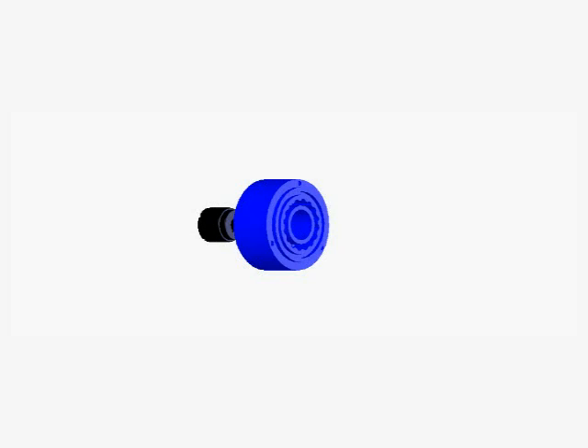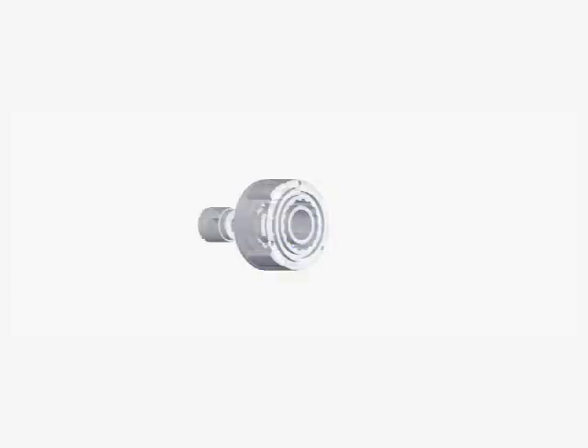DB Series pumps equipped with carbon bushings are capable of running dry for hours, the longest run dry ability of any mag drive pump in the world. For aggressive fluids or abrasives, Teflon, alumina ceramic, and silicon carbide bushing packages are available.